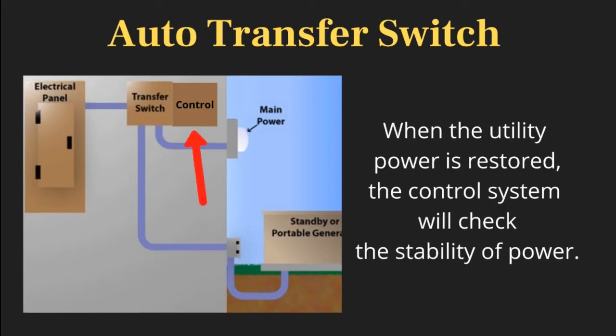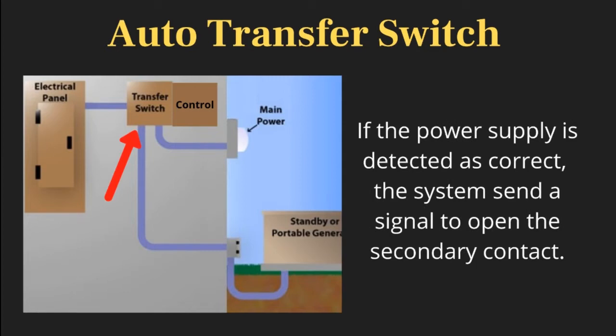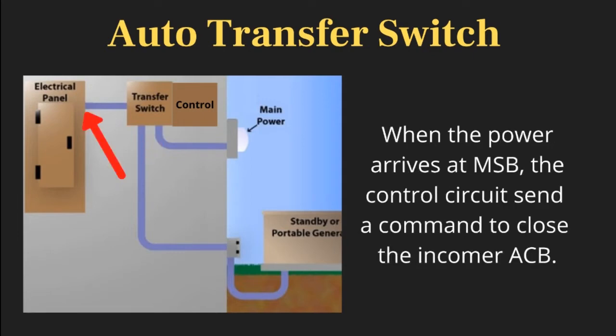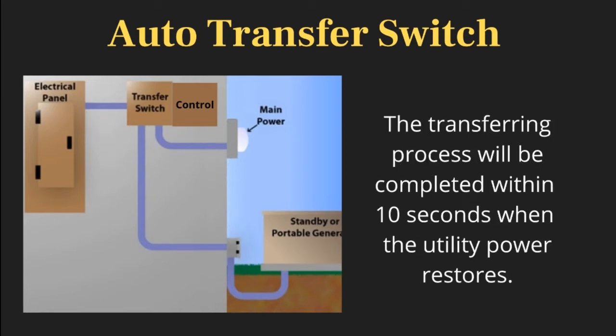When the utility power is restored, the control system will check the stability of power. If the power supply is detected as correct, the system sends a signal to open the secondary contact, stop the generator, and close the main breaker of the ATS to deliver power to the MSB. When the power arrives at the MSB, the control circuit sends a command to close the incoming ACB. The transferring process will be completed within 10 seconds when the utility power restores.